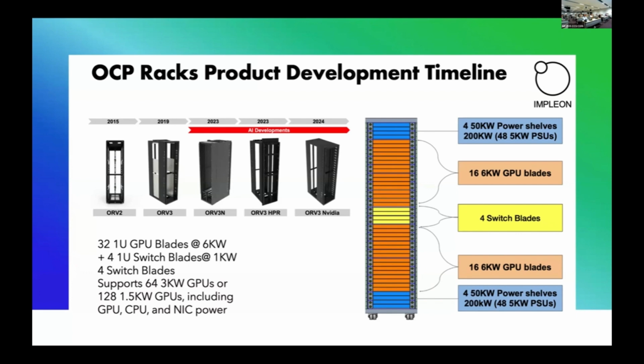Why is it so? Because in this case, we are able to put a 200 kilowatt power supply with redundancy. On the top, you see power shelves, 4 by 50 kilowatt, and below, and between them, 32 6-kilowatt GPU blades, which can have different GPU configurations, and 4 switch blades. So this is the base for the future of AI racks, because that design allows you to achieve the target. And we already see that new AI racks come with this power shelf and bus bar, and the servers don't have a power supply in themselves.